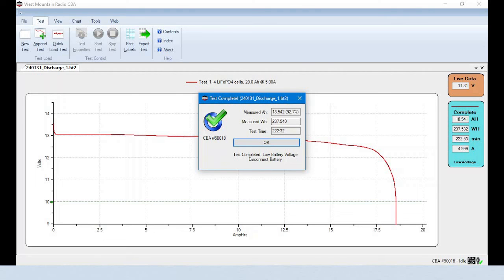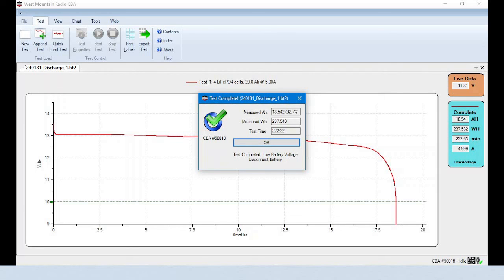A pop-up box containing a summary of the test will appear when the test is done. You can compare the total amp hour rating on the screen to the manufacturer's battery specification sheet. You may find that a battery will not attain its published amp hour rating, especially if your discharge test is conducted using different values than those used by the manufacturer. Regardless, this number can be used to determine if the battery has enough capacity to do the job you need.